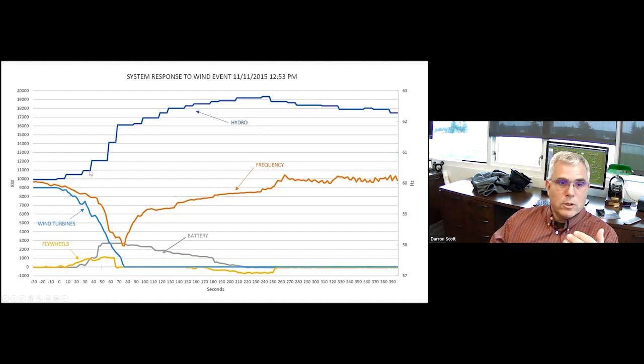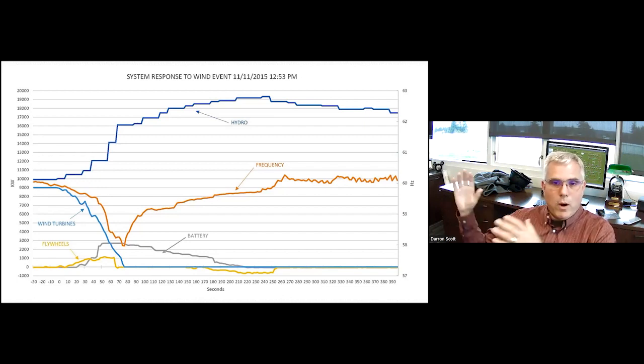Our hydro is picking up, but our hydro plant, the way it's designed, you saw the picture of the lake and then the power plant, well in between the two is a 5 mile tunnel. So hydraulically, you just can't say, hey, give me all this much more power right away, you'll end up with some hydraulic problems in the tunnel. So it takes 60, 90 seconds to really get that plant spooled up to do something like this. That's what our flywheels and batteries do, buy us that 1.5, 2, 3 minutes of gap in time to give our hydro a chance to get caught up.